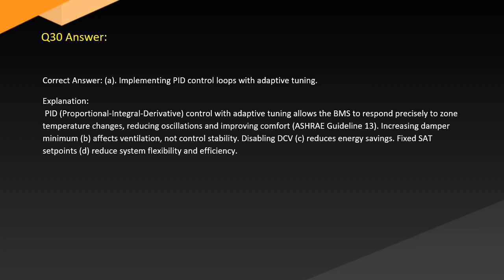Answer. Correct answer A. Implementing PID control loops with adaptive tuning. Explanation: PID (proportional integral derivative) control with adaptive tuning allows the BMS to respond precisely to zone temperature changes, reducing oscillations and improving comfort. ASHRAE Guideline 13. Increasing damper minimum, B, affects ventilation, not control stability. Disabling DCV, C, reduces energy savings. Fixed SAT set points, D, reduce system flexibility and efficiency.